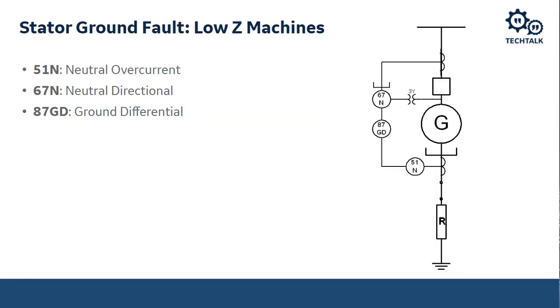For low impedance machines, we usually use three different techniques: the 51N neutral overcurrent element, the 67N neutral directional overcurrent element, and the 87GD, which is a ground differential element, very similar to the 59D third harmonic differential element we talked about, but it uses current instead. Since for a low impedance generator we have enough fault current, we're able to use these methods. We'll talk about why the 67 versus the 51N in the following slides.